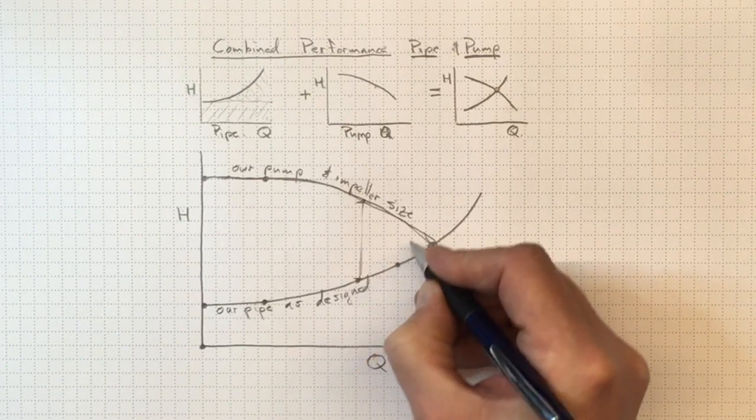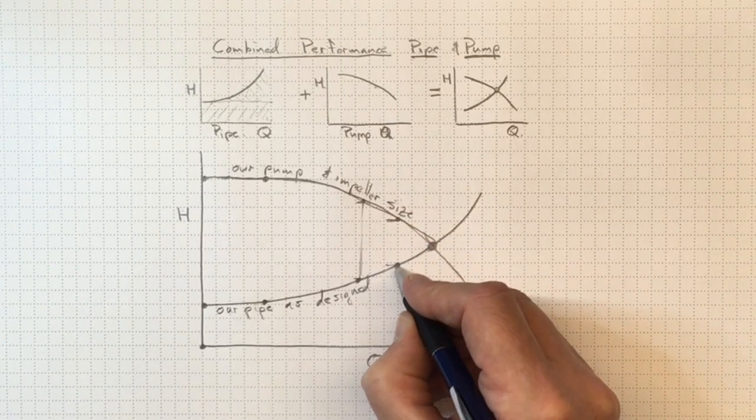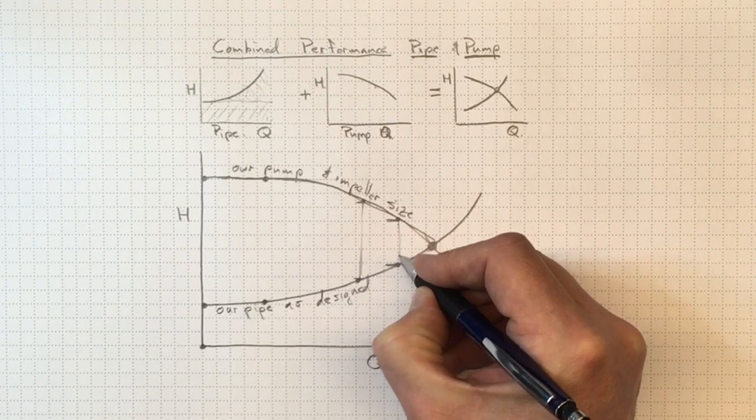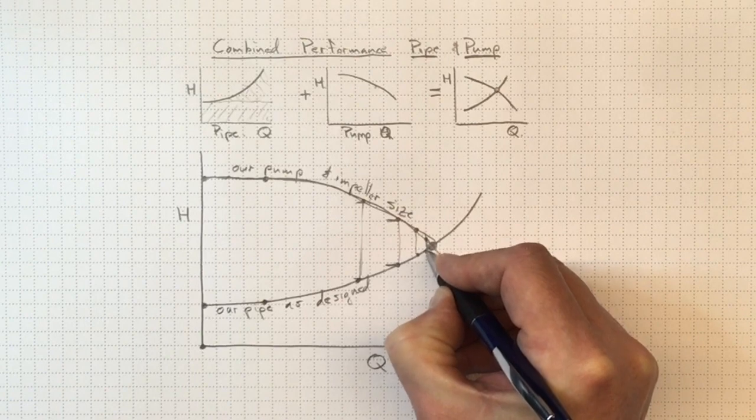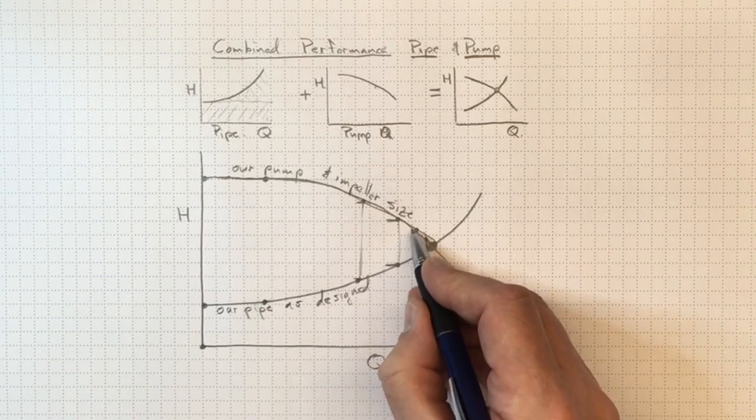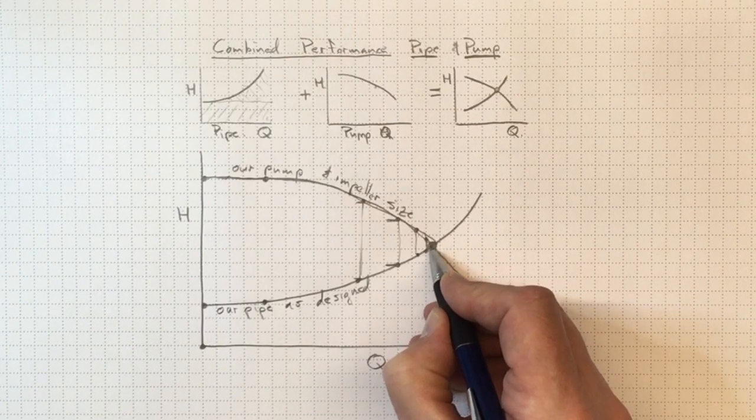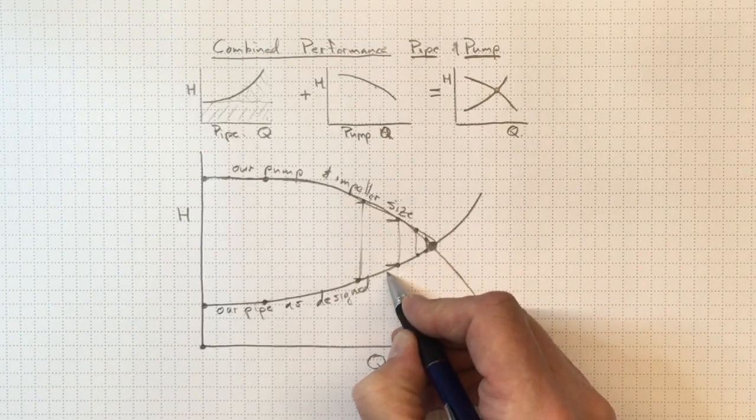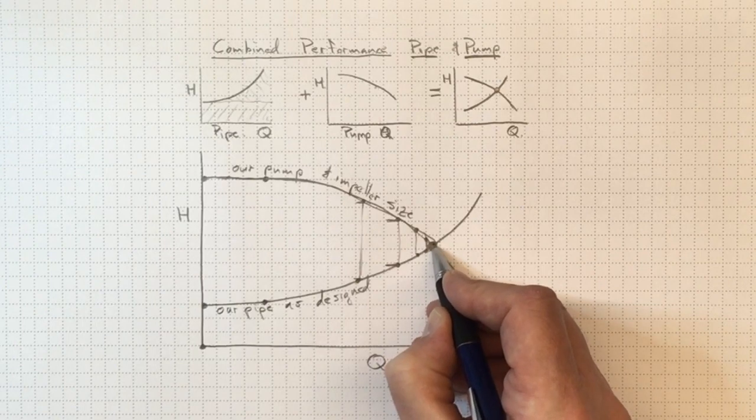But we're still going to see the flow increasing. But the difference between what the pump is providing to push the flow and the head which the piping system is resisting with, this gap is getting smaller and smaller and smaller. So eventually we'll move to the point here where we've got no difference between what the pump is delivering and what the resistance of the piping is. So now we've got no unbalanced forces on the water in the pipe. We've got an exact balance between the elevation and the losses against what the pump is putting in. And that's a stable operating point.